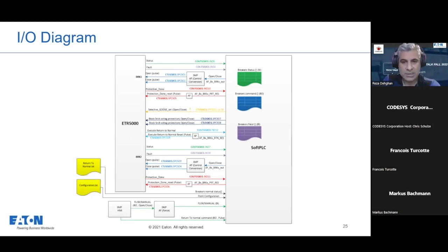Just an example, we talked about the concept of selective GOOSE or block source. They're all in the middle because they are relay related. We also have two files. We'll talk about them. If you see at the left side, the yellow boxes, return to normal TXT and configuration TXT, those two files define the configuration of our logic. Once the code is done, for every new installation we just need to change those text files to feed the new configuration to the code. We don't really need to change the code anymore.